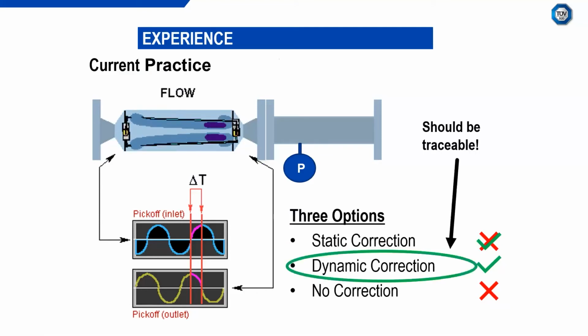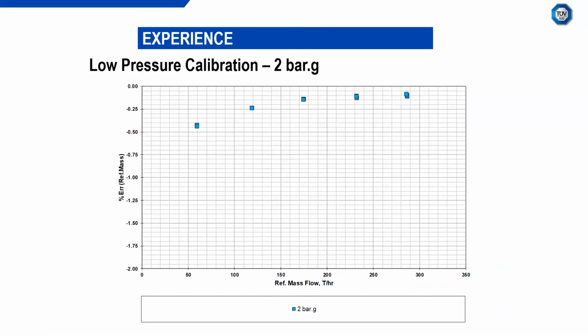One other point is if you're applying a dynamic correction, it should be traceable. Corrections are published in certain Coriolis manufacturers' data sheets, but these aren't all traceable. Certain regulators wouldn't be impressed if you were to use a non-traceable pressure correction. So try and get it from NEL or another flow facility that can operate at elevated conditions.